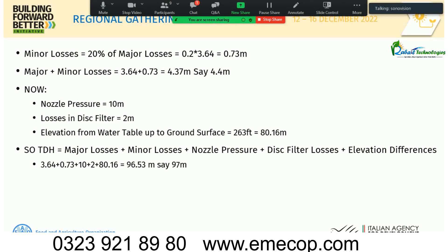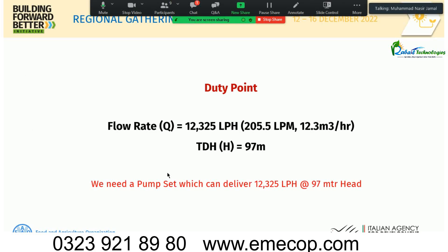Minor losses are 20% of major losses: 20% of 3.64 meters = 0.73 meters. Adding minor and major losses gives 4.4 meters. Adding nozzle pressure, filter losses, and other system losses brings the final TDH to 97 meters. Our duty point is therefore 97 meters of head at 205.5 liters per minute.